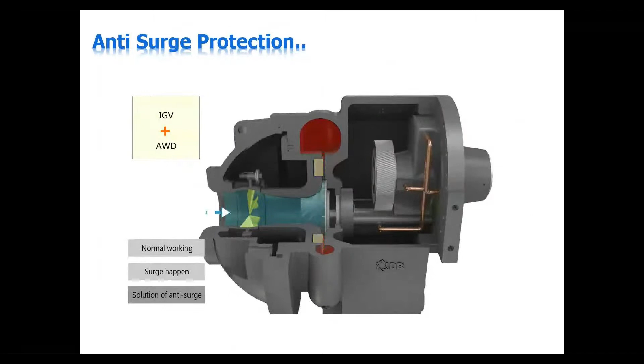This is the impeller rotating over here, and it is throwing into the volute. Now, in case of surge, it is trying to throw, but this is higher pressure, so refrigerant is flowing back. So you see how it is flowing back. The moment this happens, there is an efficiency reduction. There's a huge noise that might happen because your compressor is subjected to some kind of pressure. There could be an abnormal vibration, and there could be a current impulse. So current consumption might shoot up.